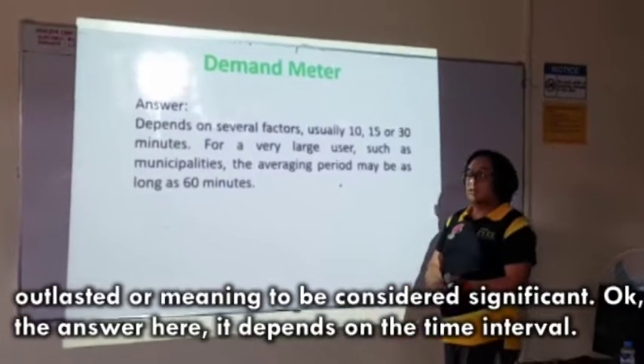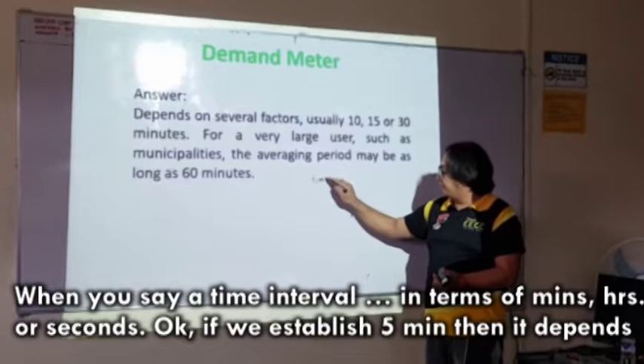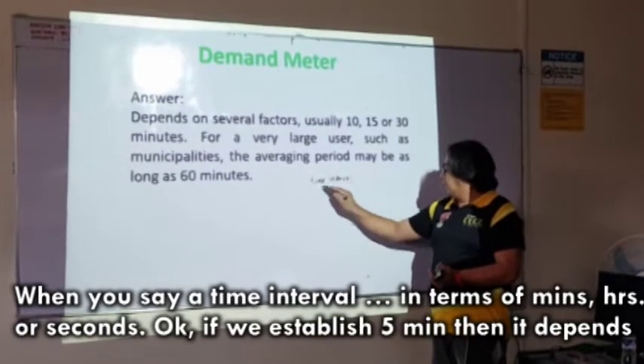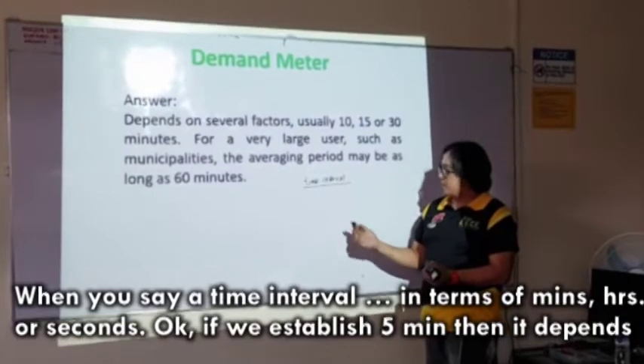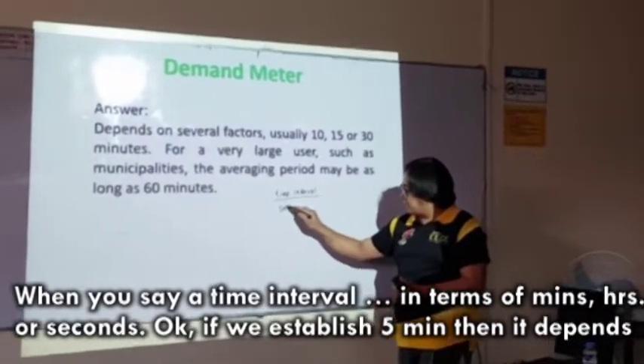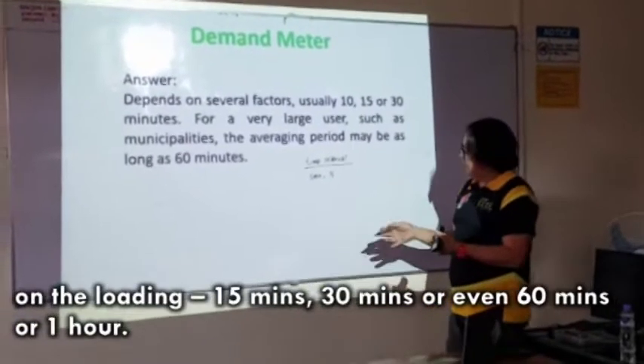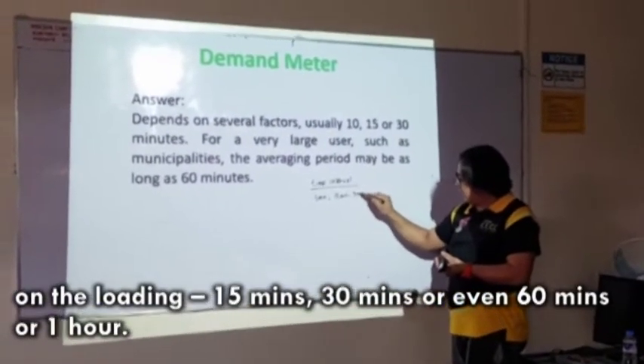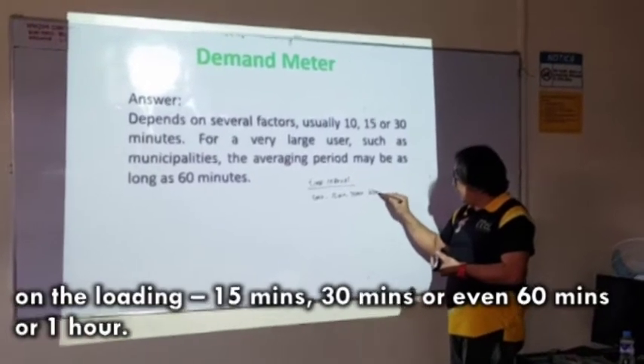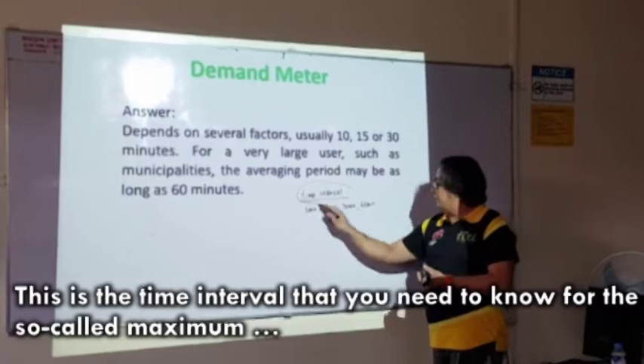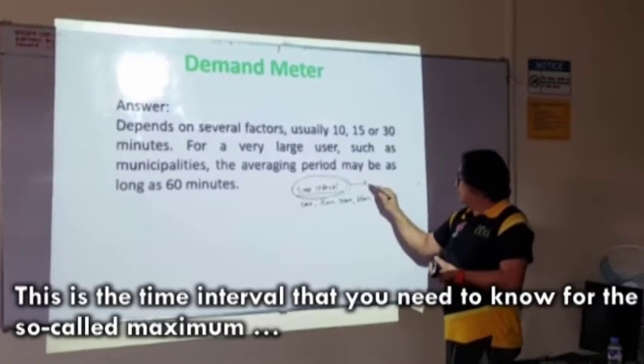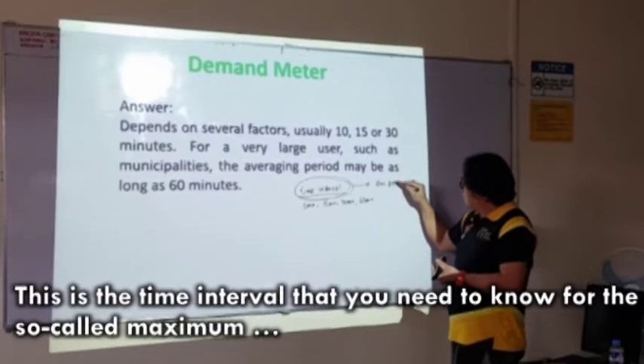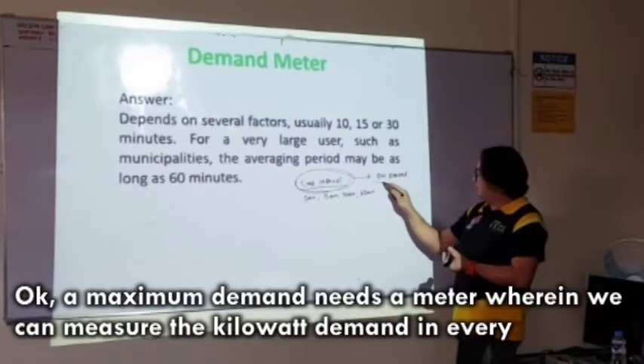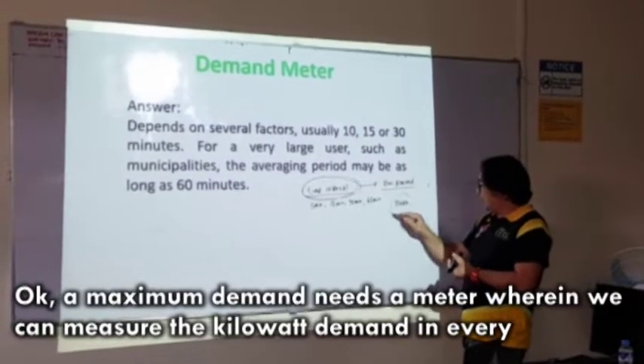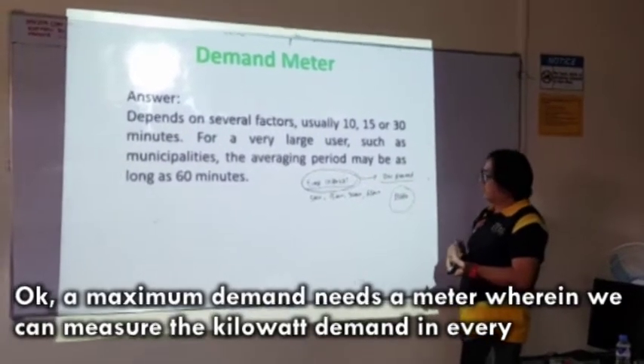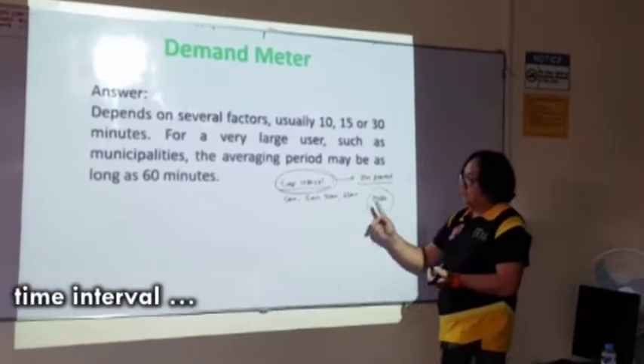The answer here depends on the time interval. When I say time interval, it could be in minutes, hours, or seconds. If we establish 5 minutes, then it depends on the loading; 15 minutes, 30 minutes, or even 60 minutes, or a 1 hour interval. This is the time interval that you need to know for the so-called maximum demand. A maximum demand needs a meter wherein we can measure the kilowatt demand in every time interval.